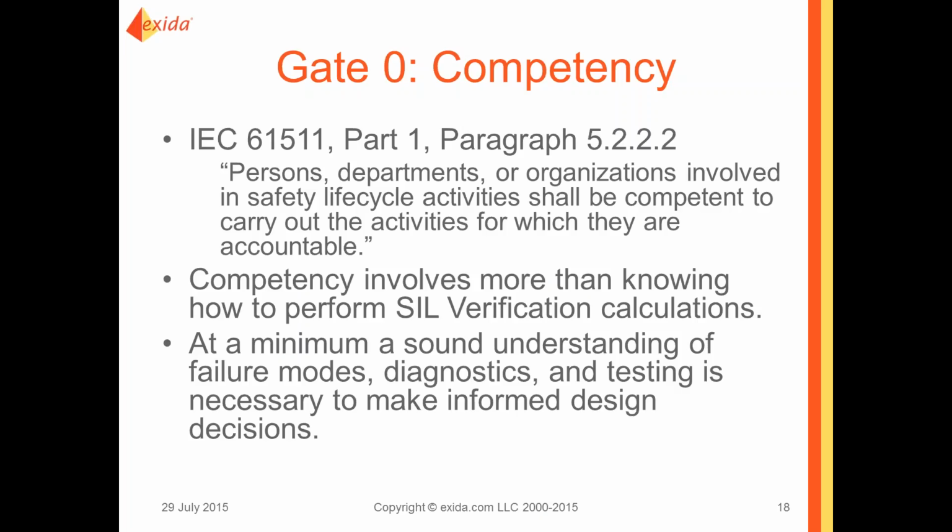Now, the SIL verification can be performed by a team or reviewed by a team, not expecting one individual to know everything, but it isn't just a matter of taking a certificate or taking a number from an OEM, putting it into a tool, and calculating a number. That would be equivalent to a carpenter who knows how to use the nail gun, having somebody tell him that, oh, you can use a 2x4 for a floor joist, and he goes, oh, I've got a piece of paper that says I can use a 2x4 for a floor joist, and I know how to put joists in, so I've built a sound floor. It's just not reasonable, and it's not defendable.